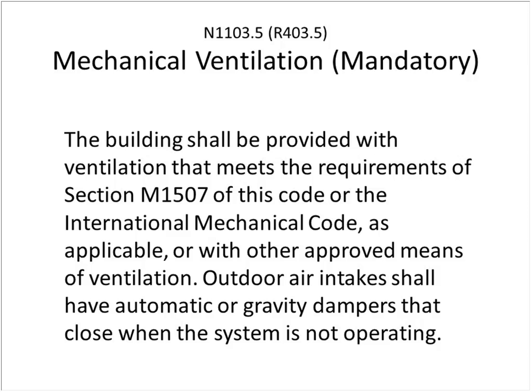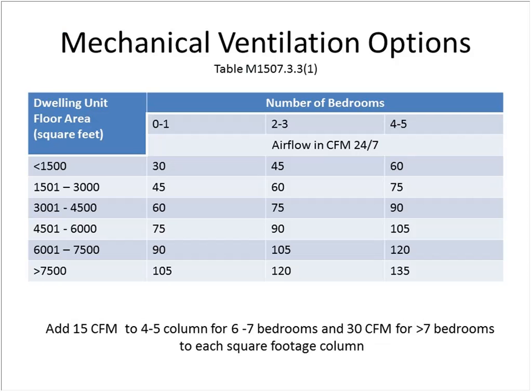And rather than discuss the options, I'm going to just say that they have fan efficacies that are required. You must meet a certain requirement for CFM per watt of power, and there are many fan options available on the market that work. Energy recovery ventilators and heat recovery ventilators are not as forthcoming in listing the fan efficacies, although I did find that the one that we see most often, RenewAire, has theirs listed as 4 CFM, which certainly meets the requirement. Others, not so much. So just be aware that there is an efficacy that's required, and make sure that your mechanical contractor provides that information to either your third-party inspector or the code officials, or better yet, to you, so that you can distribute that information as needed depending on how you meet the code.